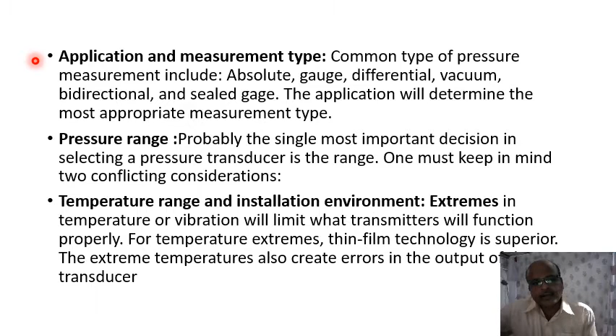Then next is pressure range. Probably the single most important decision in selecting a pressure transducer is the range. One must keep in mind two conflicting considerations: temperature range and installation environment. This is also an important parameter in pressure sensor selection. Extremes in temperature or vibration will limit what transmitters will function properly. For temperature extremes, thin film technology is superior. The extreme temperature also creates errors in the output of the transducer. So these are the parameters while selecting a pressure sensor.